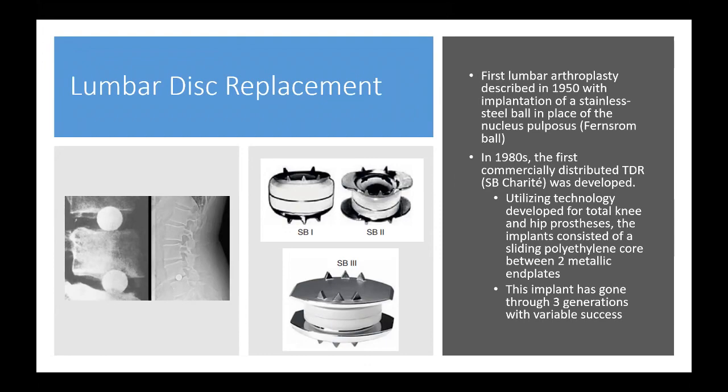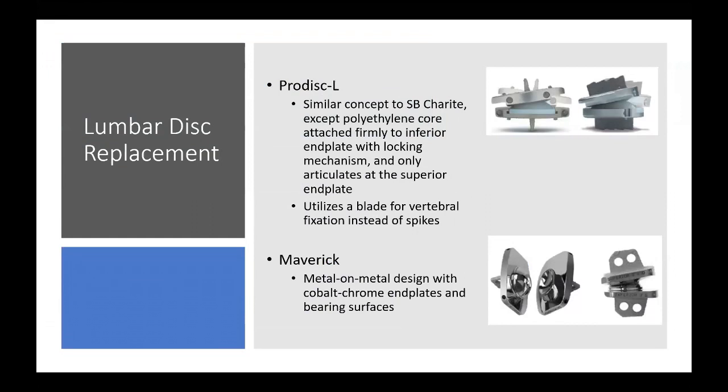Ultimately the Charité was shut down not due to problems but because of a competing device. The Prodisc-L was a similar concept except the polyethylene core is attached firmly to the inferior end plate with a locking mechanism — similar to a total knee — and only articulates with the upper end plate. It used a blade for caudal fixation instead of spikes. The Maverick is a metal-on-metal design with cobalt chrome end plates and bearing surfaces.